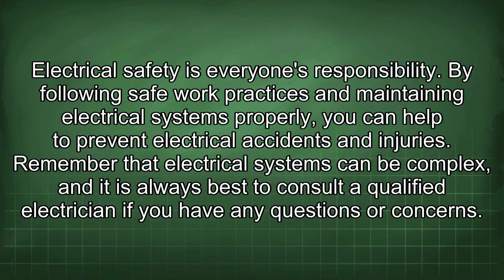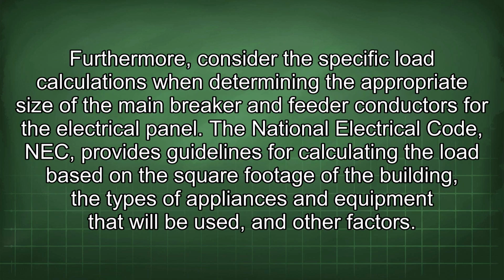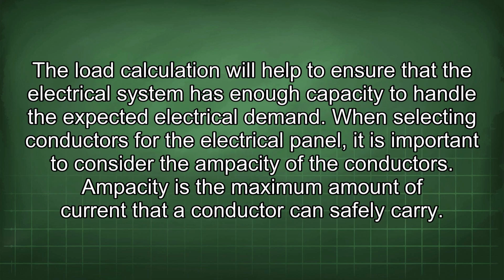Remember that electrical systems can be complex, and it is always best to consult a qualified electrician if you have any questions or concerns. Furthermore, consider the specific load calculations when determining the appropriate size of the main breaker and feeder conductors for the electrical panel. The National Electrical Code, NEC, provides guidelines for calculating the load based on the square footage of the building, the types of appliances and equipment that will be used, and other factors. The load calculation will help to ensure that the electrical system has enough capacity to handle the expected electrical demand.